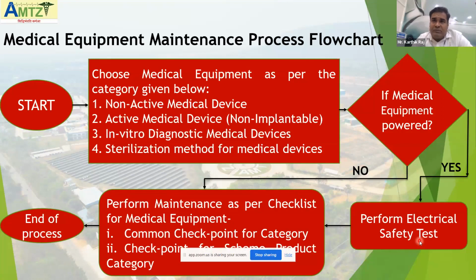In the hospital, what we can do is, let's say you have bought a patient monitoring system. The first time you buy the patient monitoring system and it is going to be installed, you can tell the manufacturer to perform the IEC 60601-1 test. You can put that as an acceptance criteria. It's not that you will go with that result afterwards. It's an acceptance criteria test when you are accepting equipment in the hospital.